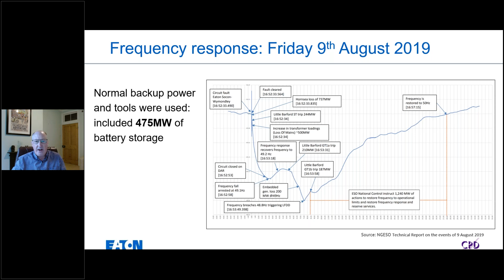So I think I've spent quite a bit of time on that slide and explained it in some detail. I think really the key takeaway from this is that fast-acting flexible energy resources are absolutely critical to maintaining the operation of the power system. And clearly we didn't have an adequate amount of resource when this event occurred in 2019. And as we have higher renewables penetration, as that system inertia reduces, it will become imperative that we continue to increase the base of flexible energy resource that we have that has the capability to respond very, very rapidly.